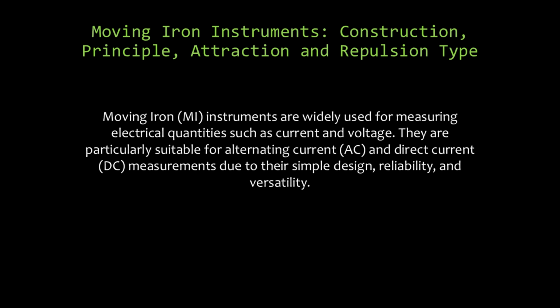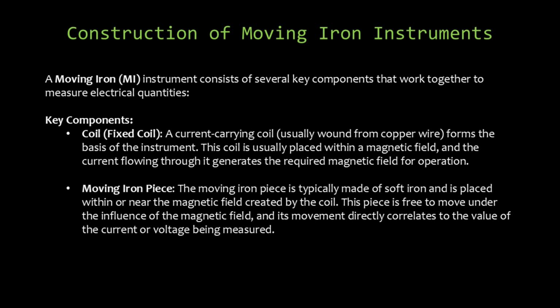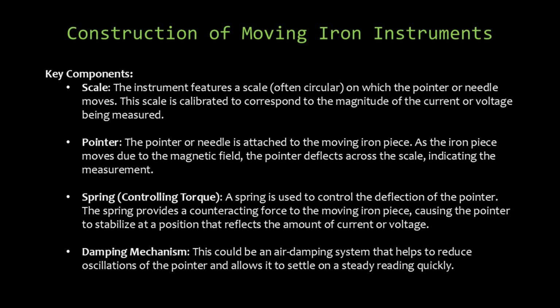This design offers remarkable adaptability, making moving iron instruments crucial in industrial and scientific settings where measurement reliability is paramount. The construction of moving iron instruments is a masterpiece of electromagnetic engineering. At its core, the instrument comprises several critical components working in harmony. A fixed copper wire coil generates the magnetic field, while a soft iron piece, carefully positioned within this field, provides the measurement mechanism. The scale and pointer work together to translate magnetic interactions into readable measurements.